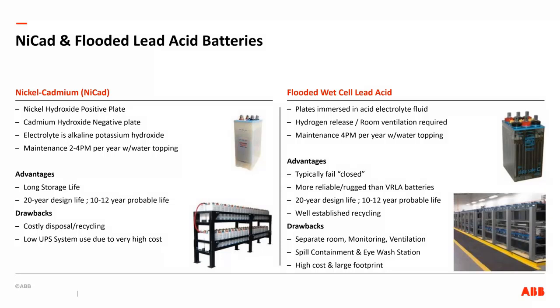The drawback, and the reason we still see them, is that there are still customers, especially in the financial world, that swear by the flooded wet cell batteries. But they require separate battery rooms. They require hydrogen monitoring. They require ventilation. They require spill containment. They require eyewash stations. They take a lot of space. They're big. They're heavy. They require a lot of maintenance. Also, somebody has to run around and top up the water. That was a given a couple of decades ago. It's been less and less.